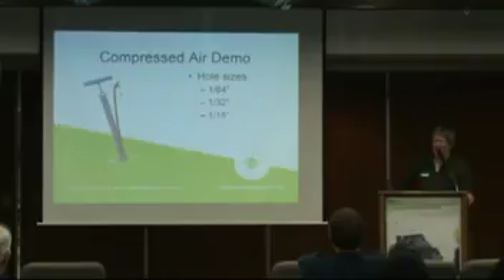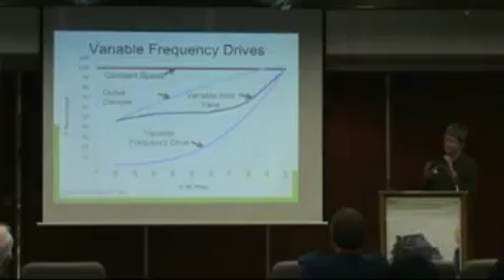If you move airflow by controlling dampers or valves, you get a little bit of savings. But if you can do it by slowing down your motor, you can have huge savings. If you look here, we've cut down our airflow by just 20%, so we still have 80% of our airflow. If you're on a variable frequency drive, you've cut down to 50% of your power input. So there's huge savings available there, and we hit on that one quite carefully.